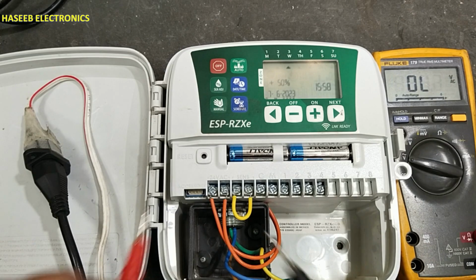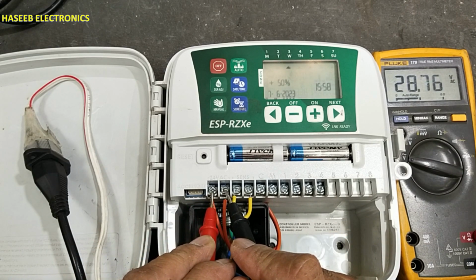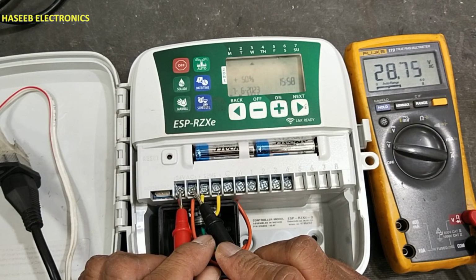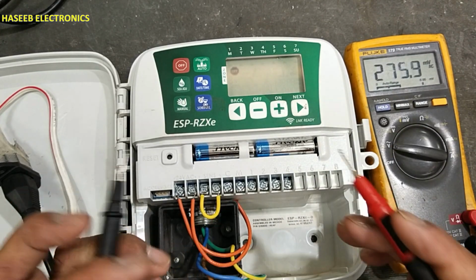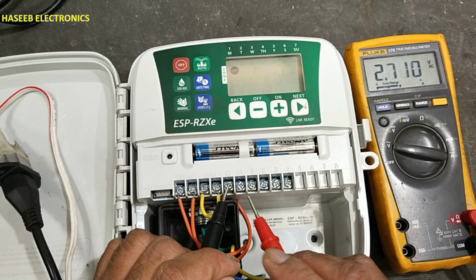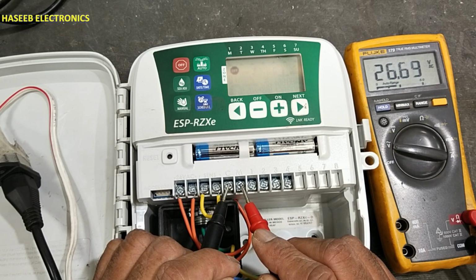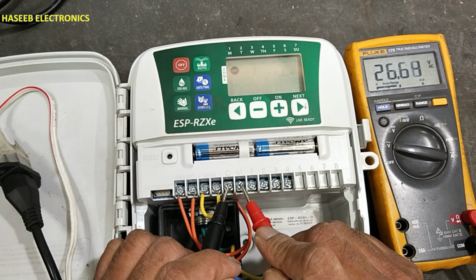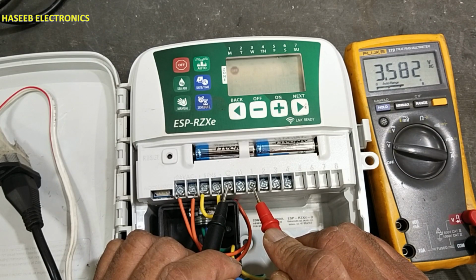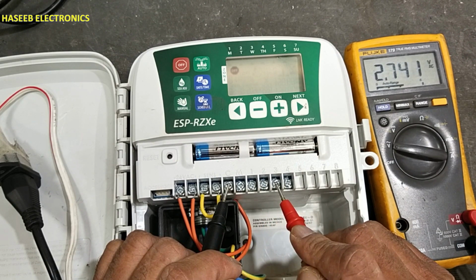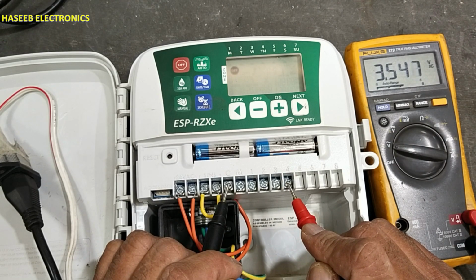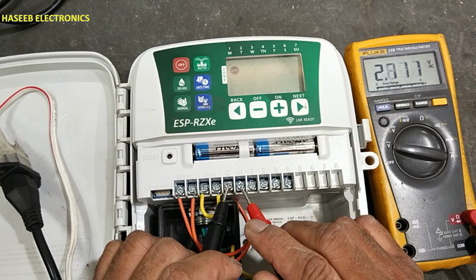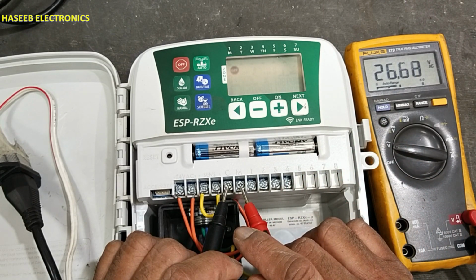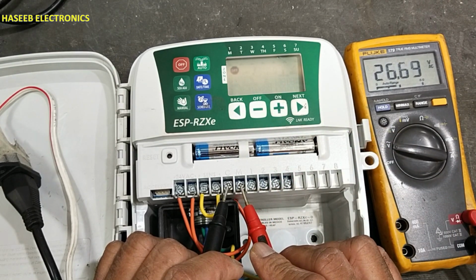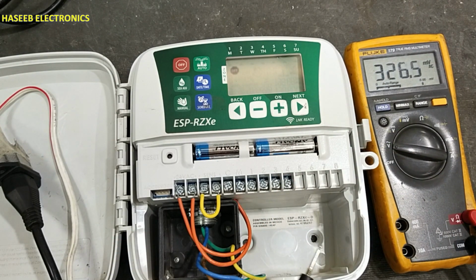Set the multimeter to AC and we will check voltage at this point. 28 volt AC, that's good. Now we will place the common lead at common, and this lead at the master valve. It is providing 26 volts. Here no voltage, no voltage, no voltage, no voltage. This condition is bad. When the system is off, it must remain off. So this is our first problem.